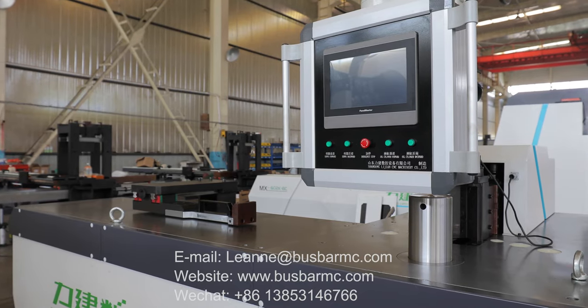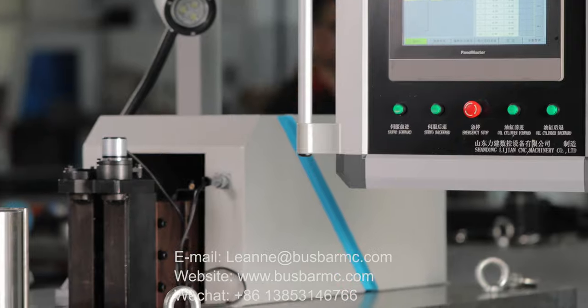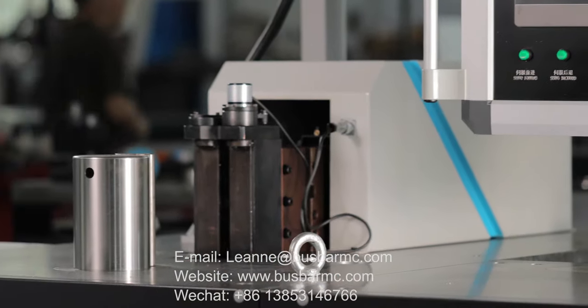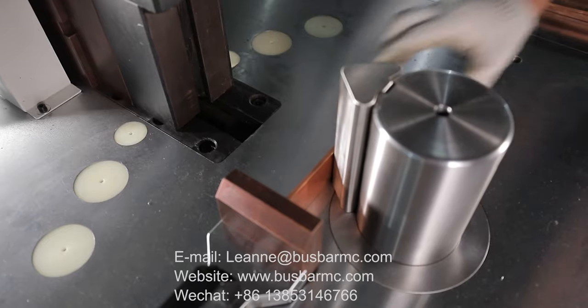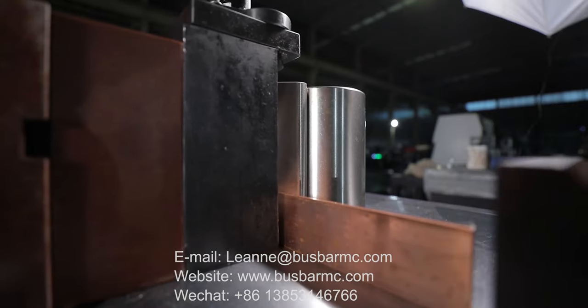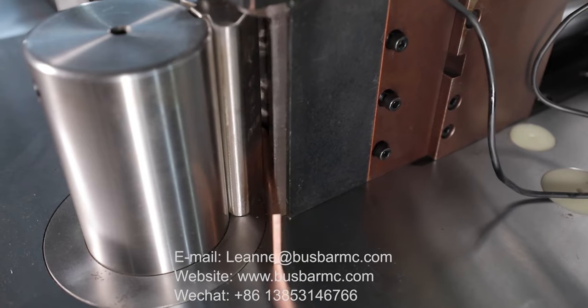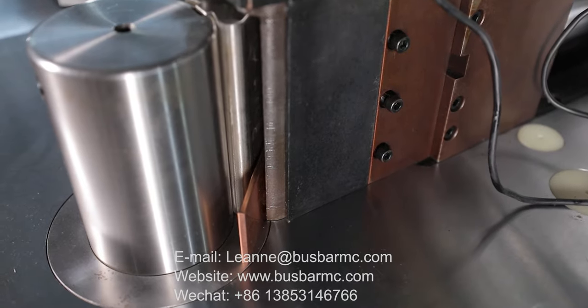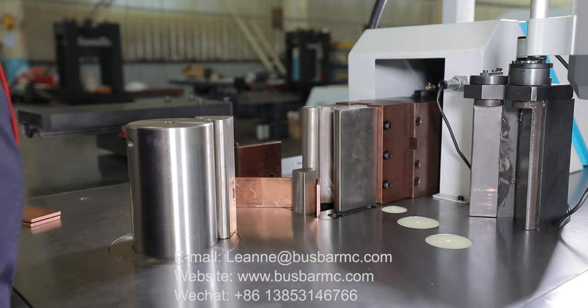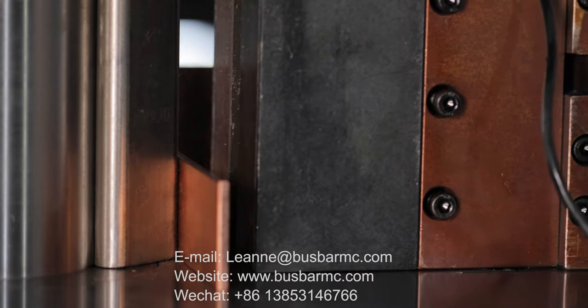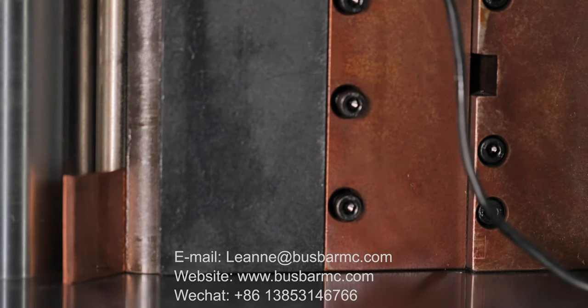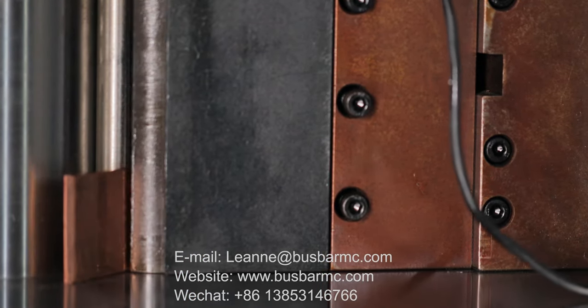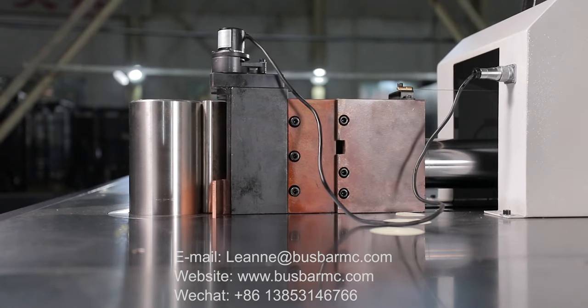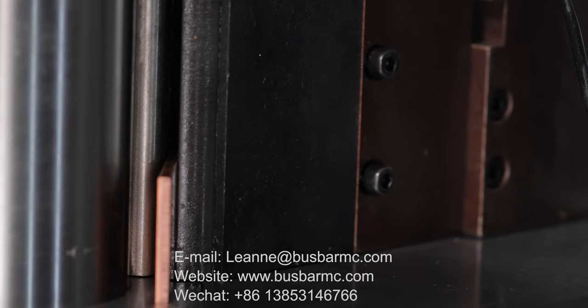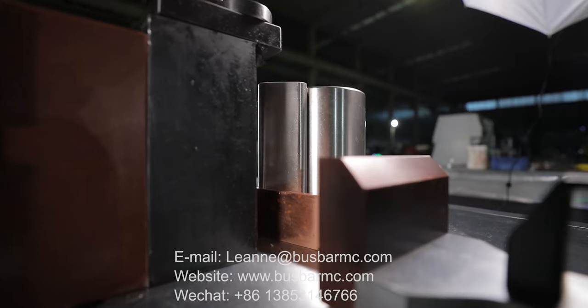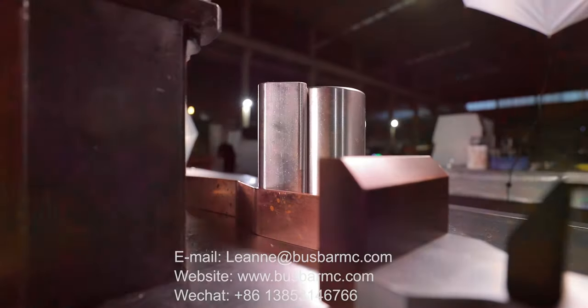The structure of the machine adopts an upper open type, which can conveniently take and place busbars, and the bending power is supplied by double pumps to ensure bending efficiency and bending precision of the machine. The gauge of the machine is servo controlled, and the position can be adjusted manually according to the need, which can easily realize the control of the position of the busbars during the work of flat bending and vertical bending. The machine also can be equipped with an electronic die system that detects busbar bounce according to customer requirements.